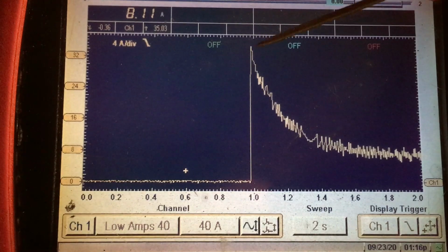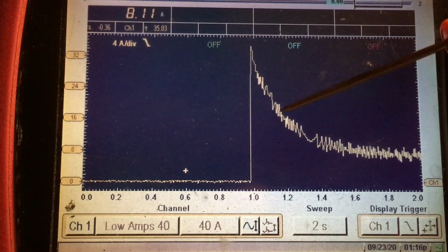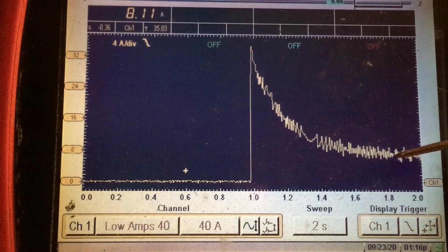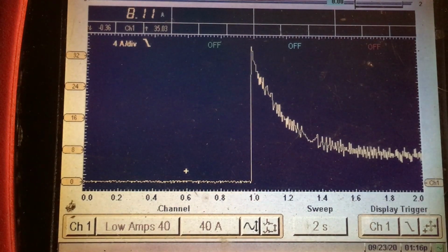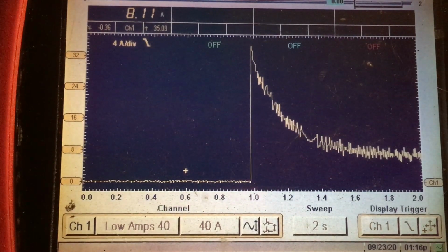And then as the speed starts to ramp up, we have this gradual slope down in the waveform, and then the blower eventually reaches its nominal operating speed around here, drawing around 8 amps. Does that make some sense, boys? I hope so. That looks completely normal to me. That's what I would expect to see.